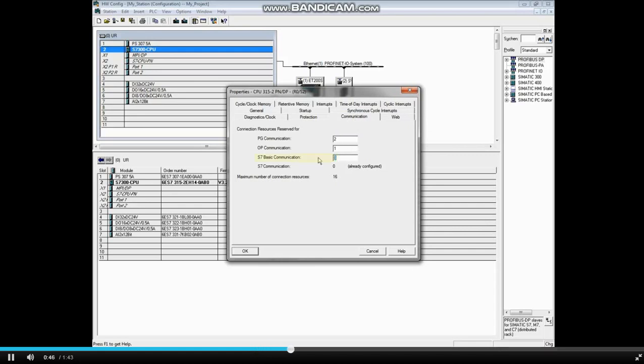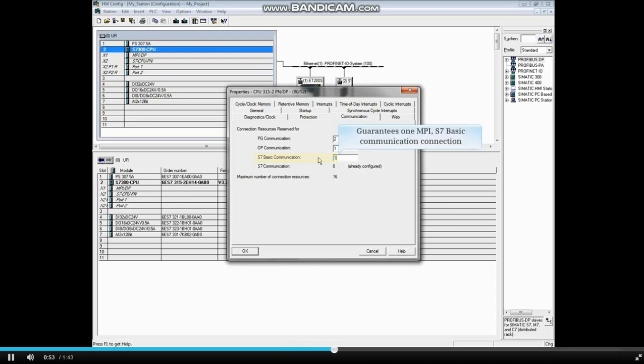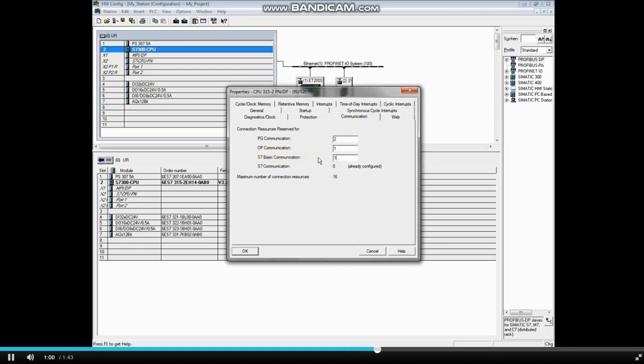S7 Basic Communication is carried out over the Multi-Point Interface or MPI Network. Reserved connections for communication blocks, such as for client-server communication, guarantee a connection will be available. S7 Basic Communication is typically not reserved but allowed to take up resources as they are needed and release them when they are done.